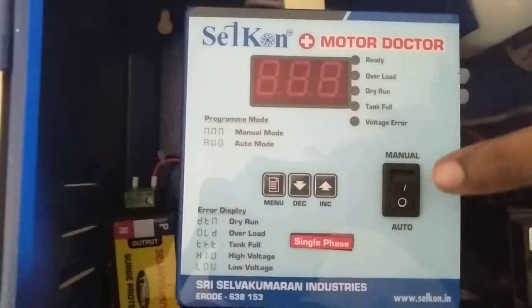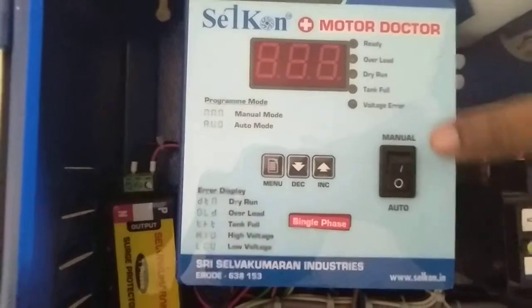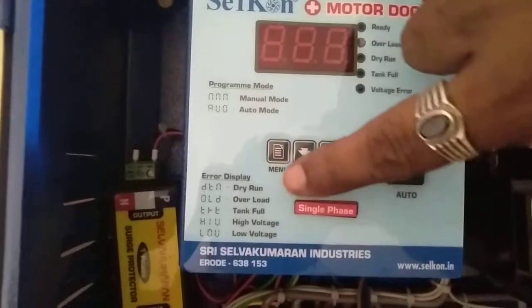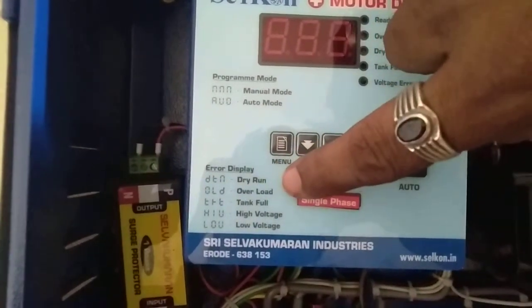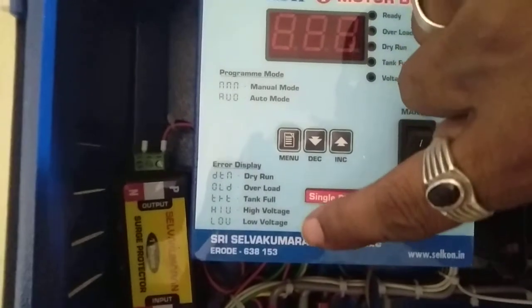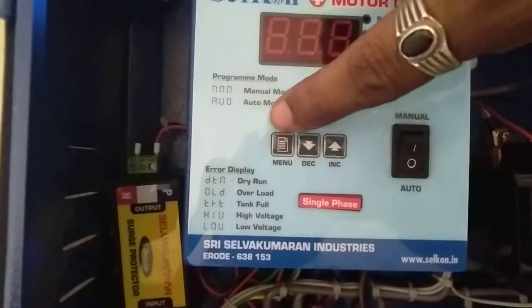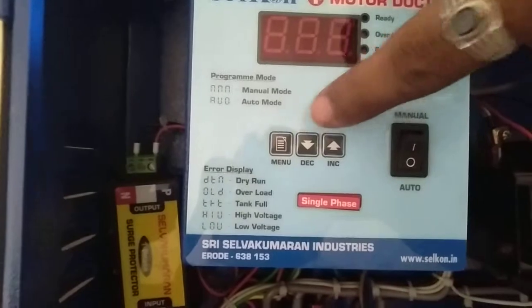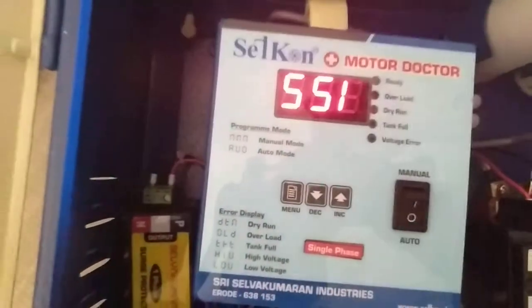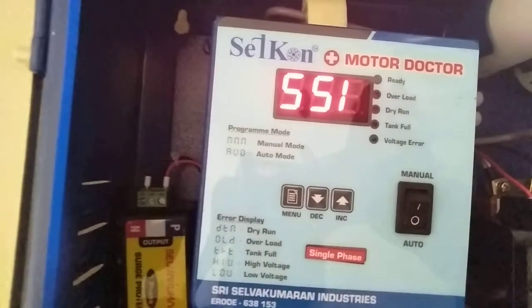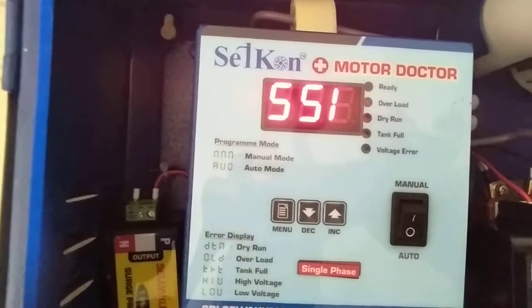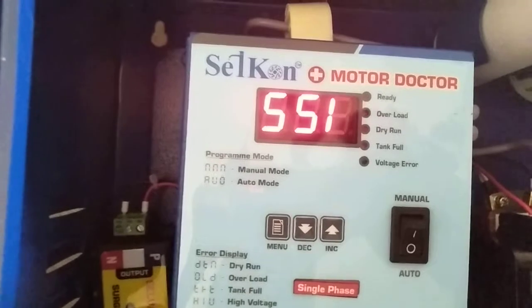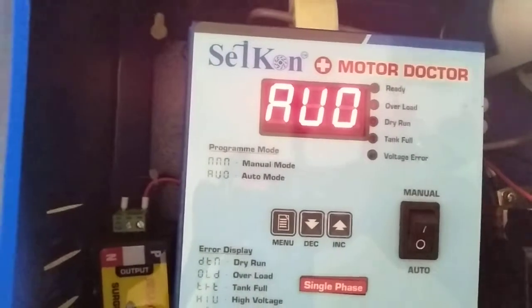SELKON motor doctor. This is auto mode, manual mode, and the functions: dry run, overload, tank full, high voltage, low voltage. And these are the main functions: menu, decrement, increment. Now I can switch on the controller. Now we can see SSI. SSI actually means Sri Selvakumaran Industries. Now the controller will be switched on in auto mode.